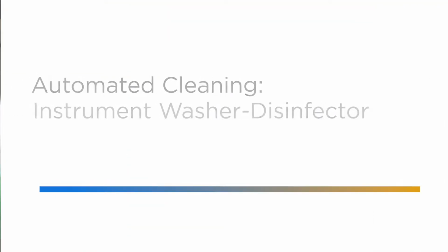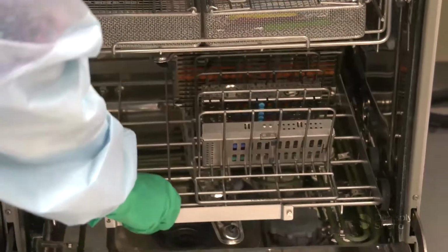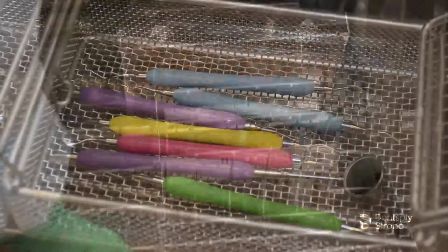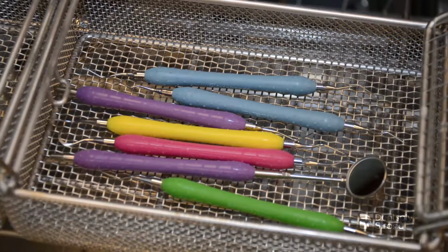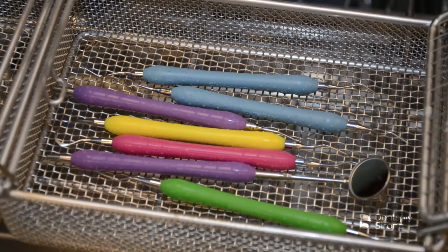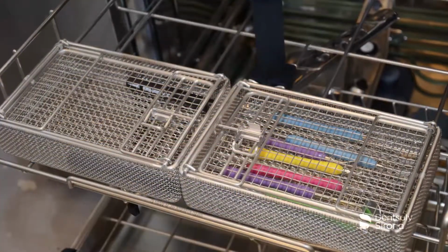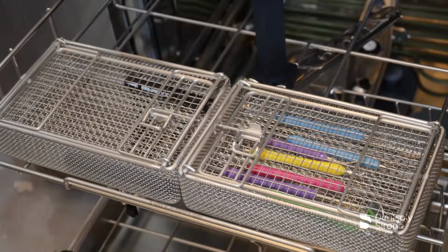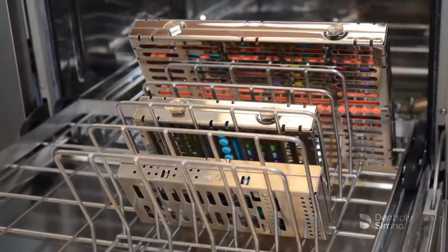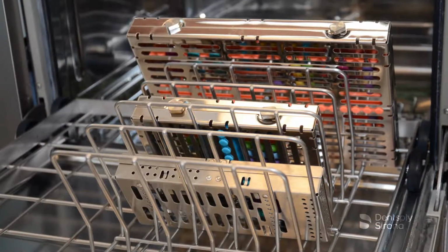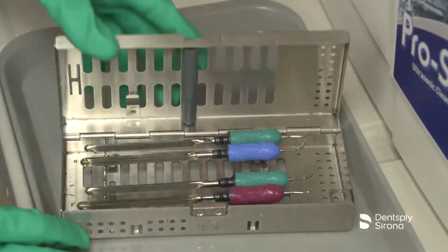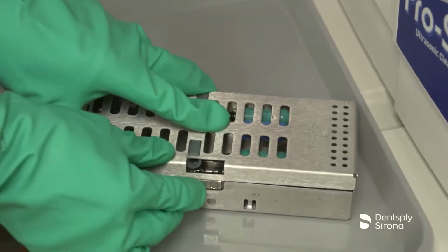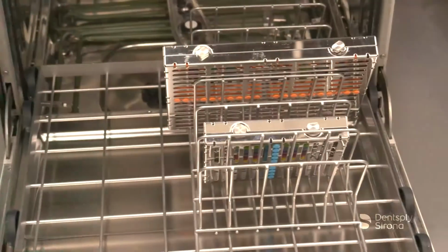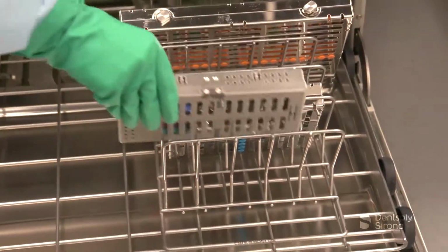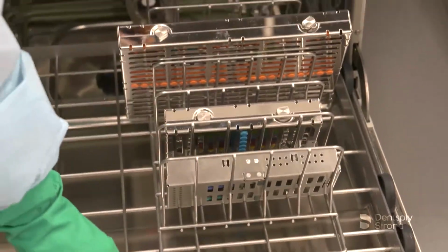When using an instrument washer disinfector for cleaning and disinfection of instruments, always follow the manufacturer's instructions for use for the unit and instrument washer solution, making sure to observe the concentration rates and contact times as well as the instrument washer's recommended cleaning and/or thermal high-level disinfection cycle. The use of an instrument cassette during an automated cleaning disinfection is recommended to reduce the risk of instrument damage. Place the cassette into the instrument washer and begin the washer disinfector cycle.